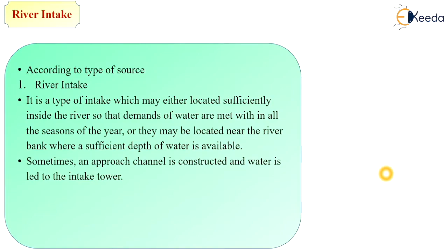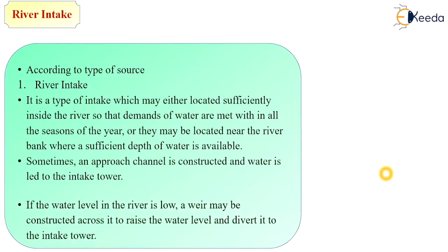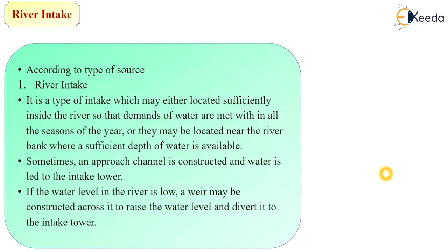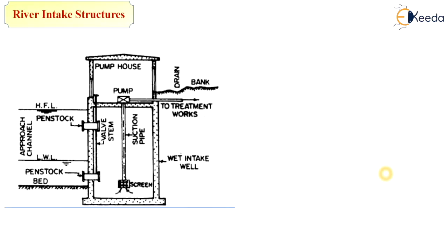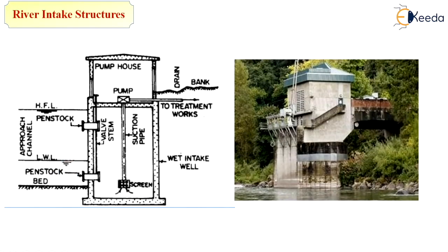River intake structures are constructed under or along the river. Sometimes an approach channel is constructed and water is led to an intake tower. If the water level in the river is low, a weir may be constructed across it to raise the water level and divert it to the intake tower. As seen in the typical diagram, the low water level and high flood level are shown, with a penstock for water entry. A screen is provided to avoid floating and silt materials, and a suction pipe sucks the clean water through a pump and conveys it to the treatment plant.